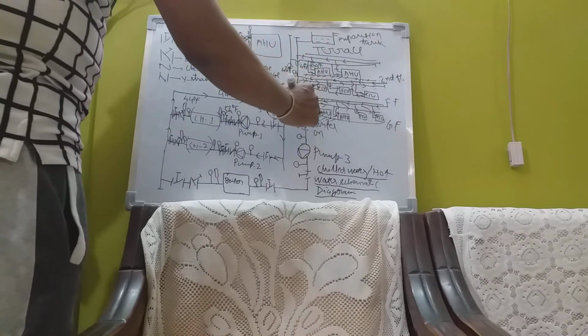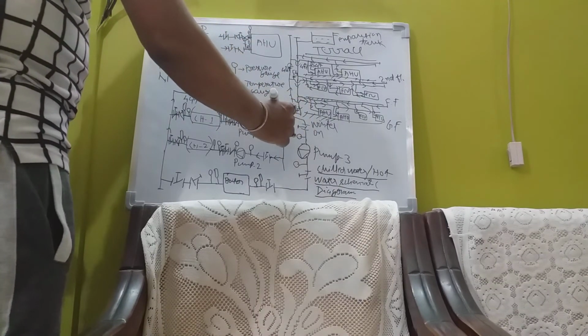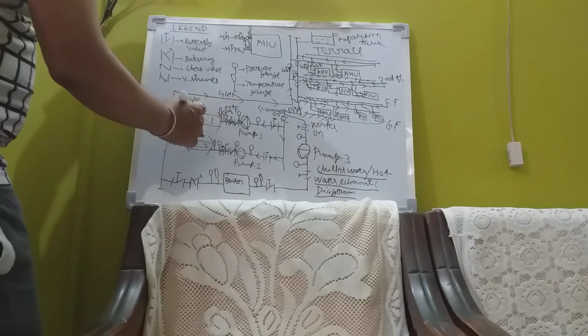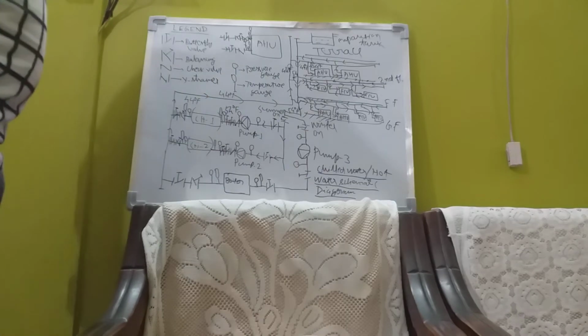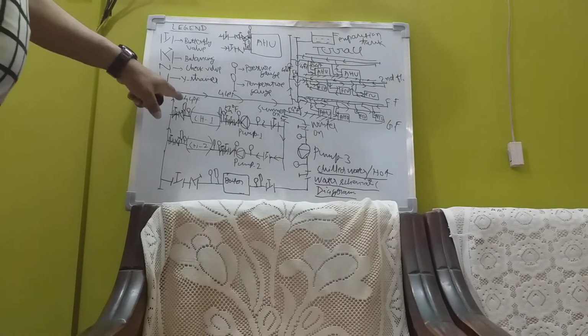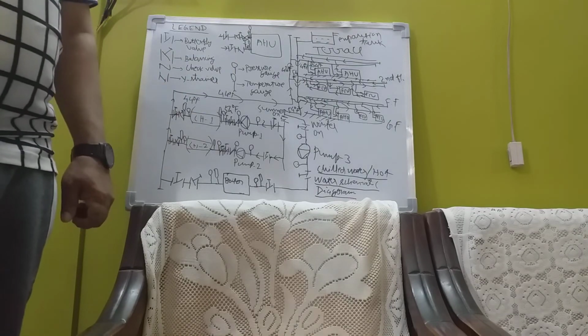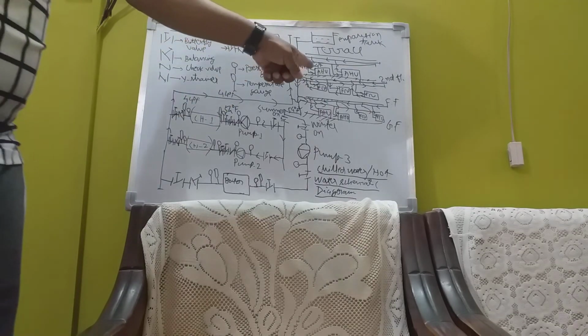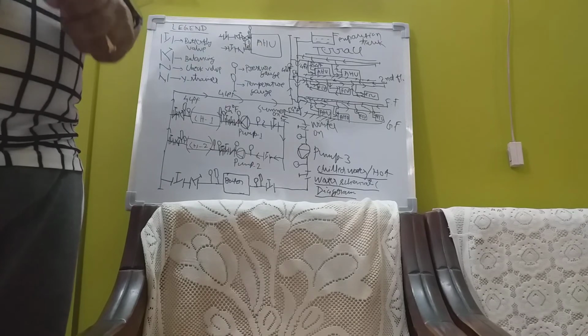See, it is 54 degree Fahrenheit. At 54 degree Fahrenheit, the chilled water comes in, takes a delta T of 10 degree drop, goes at 44, and again comes back. Same delta T, 10 degree, rising in the AHU.